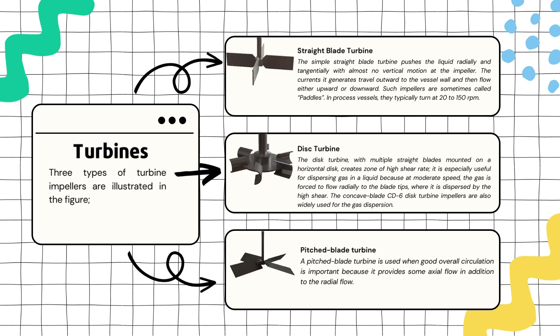The next type of turbine is a pitched blade turbine. The pitched blade turbine is chosen when you need good overall circulation, not just radial flow. It provides a combination of both axial and radial flow, meaning up and down flow and outward flow.